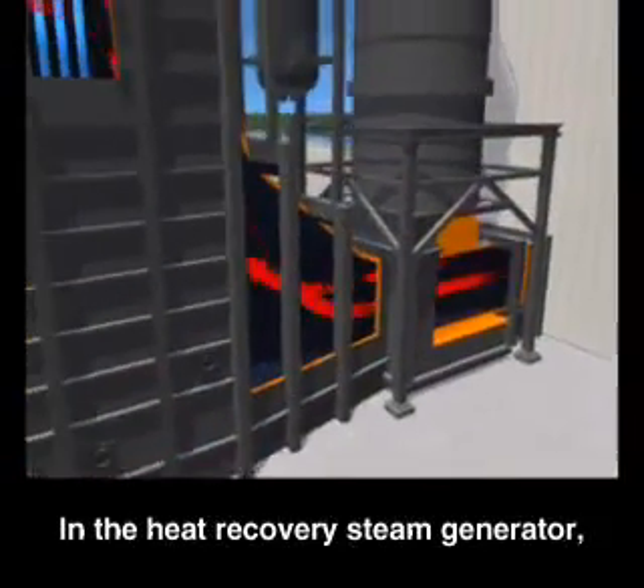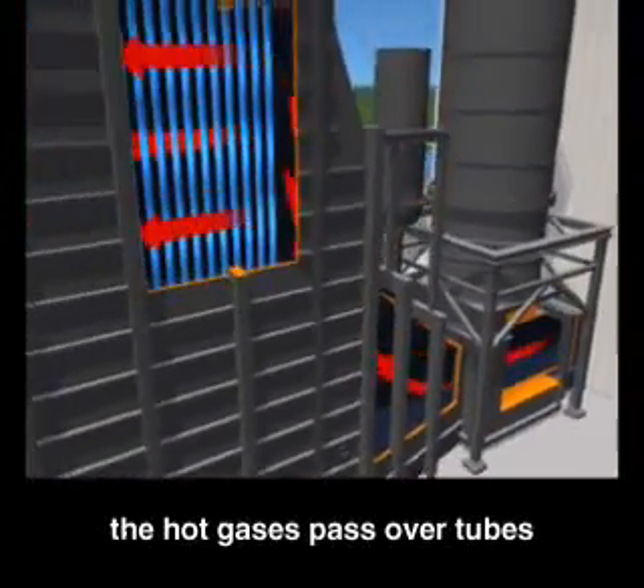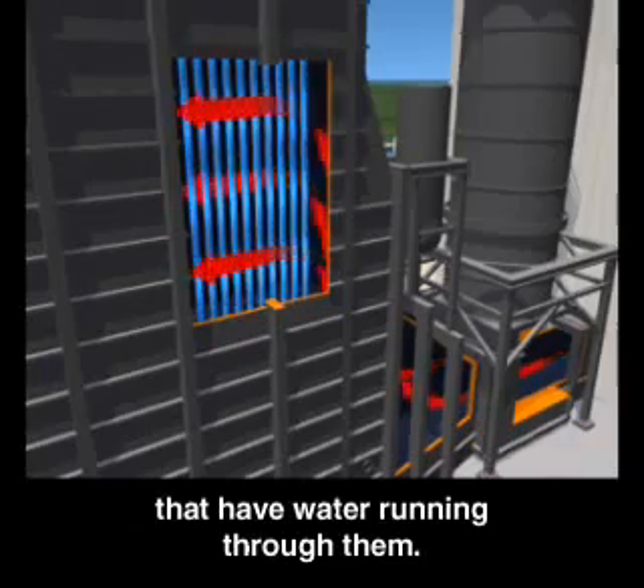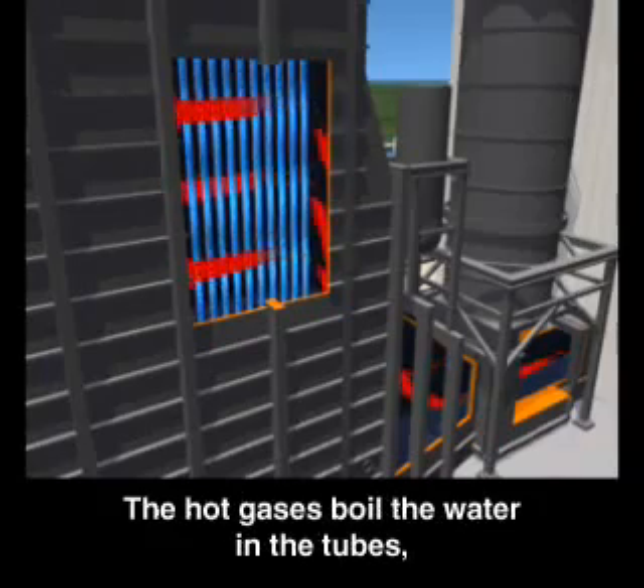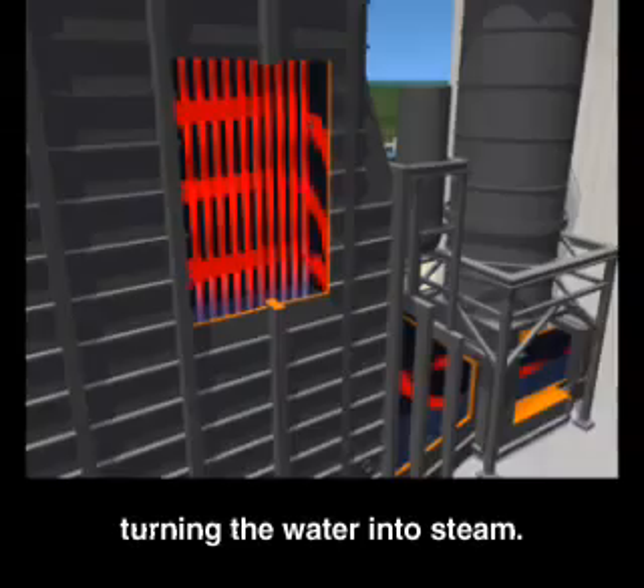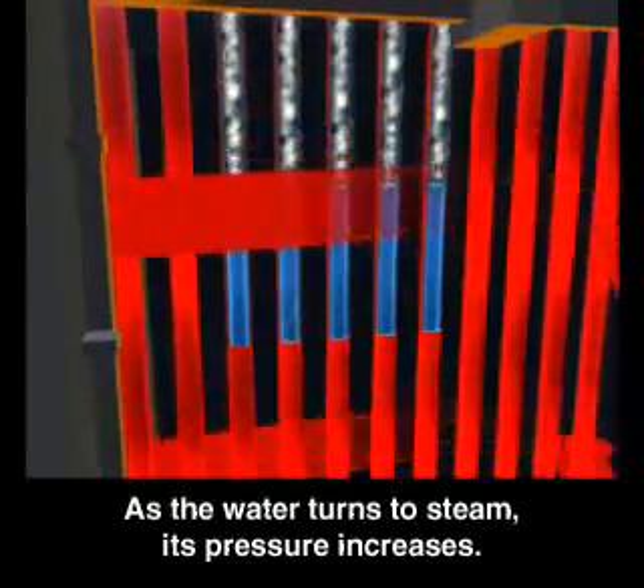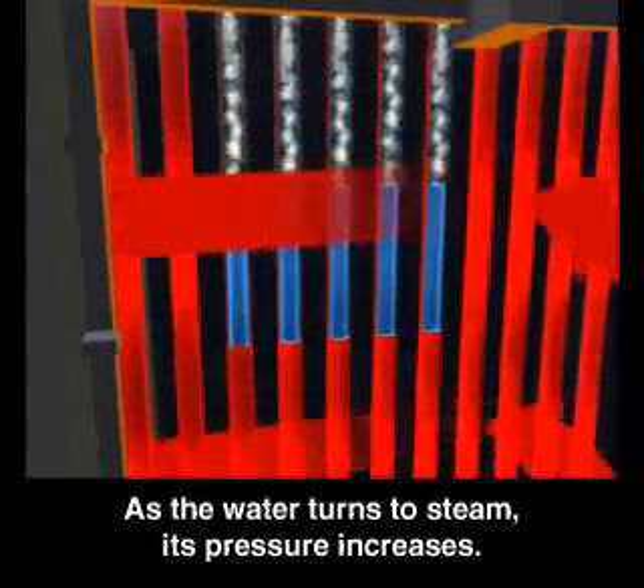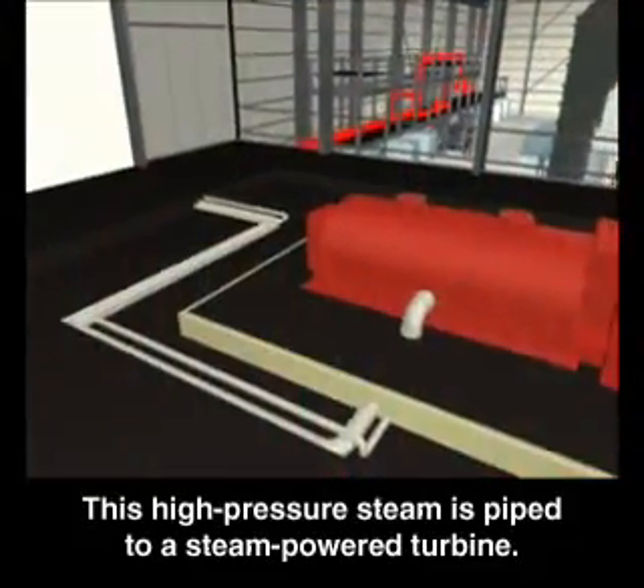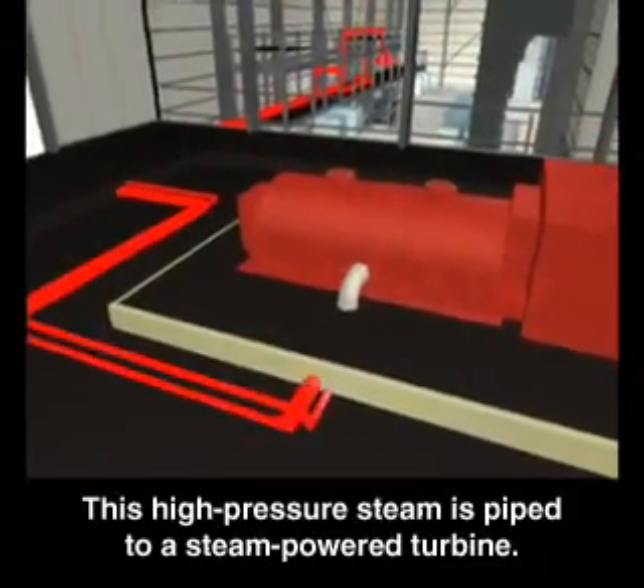In the heat recovery steam generator, the hot gases pass over tubes that have water running through them. The hot gases boil the water in the tubes, turning the water into steam. As the water turns to steam, its pressure increases. This high-pressure steam is piped to a steam-powered turbine.